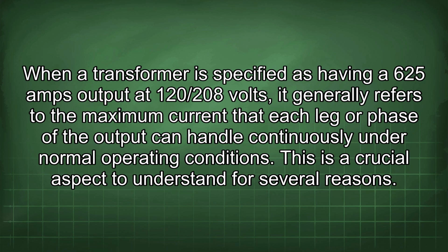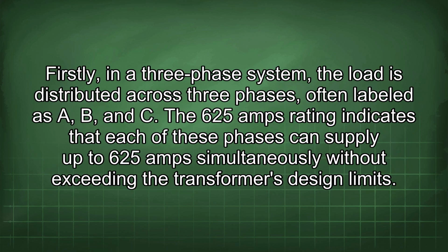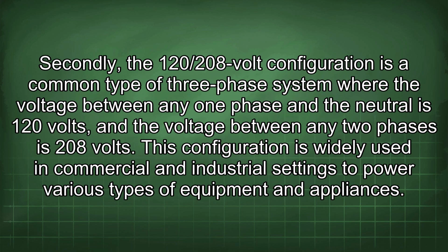This is a crucial aspect to understand for several reasons. Firstly, in a three-phase system, the load is distributed across three phases, often labeled as A, B, and C. The 625 amps rating indicates that each of these phases can supply up to 625 amps simultaneously without exceeding the transformer's design limits. Secondly, the 120/208 volt configuration is a common type of three-phase system where the voltage between any one phase and the neutral is 120 volts, and the voltage between any two phases is 208 volts. This configuration is widely used in commercial and industrial settings to power various types of equipment and appliances.